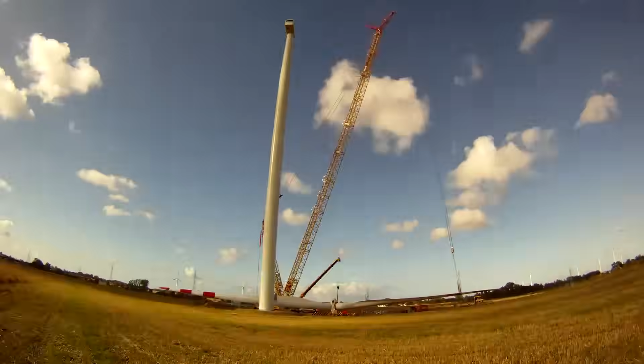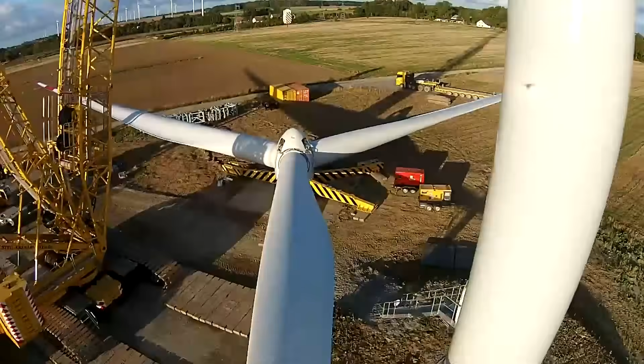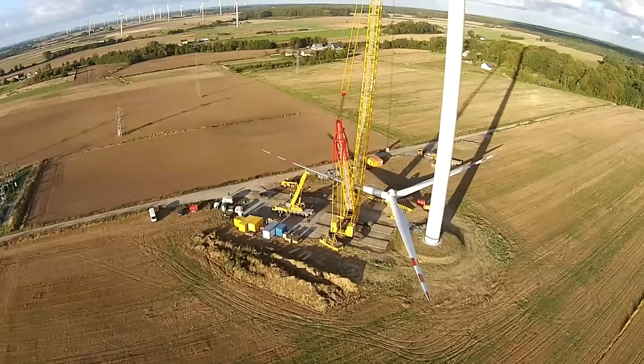Electrical infrastructure was developed in tandem with turbine installation. Each turbine was connected via underground medium voltage cables to pad-mounted transformers, which stepped up voltage for transmission to a central substation. The substation, constructed on a separately graded pad, featured power transformers, circuit breakers, protection relays, and SCADA systems to monitor and control generation output.